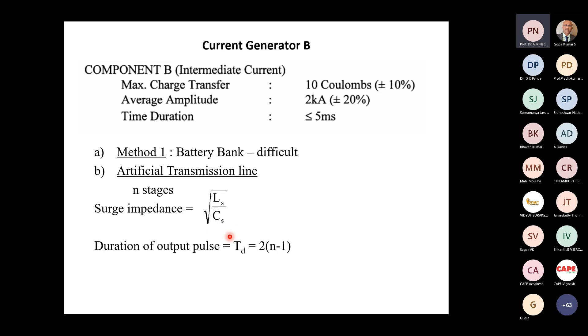10%. Current is 2 kiloamperes, duration less than 5 milliseconds. A battery bank is a considered option. I've seen it at the University of Hanover; they had a battery bank to generate this wave shape, but it's not very easy to maintain a huge lot of batteries. Therefore, what we did was consider an artificial transmission line, consisting of a ladder network of C and L like this.